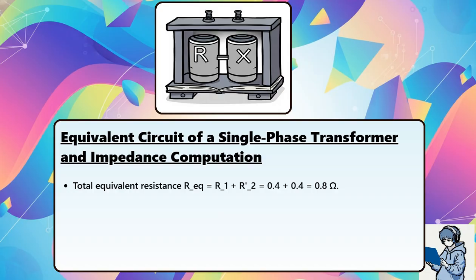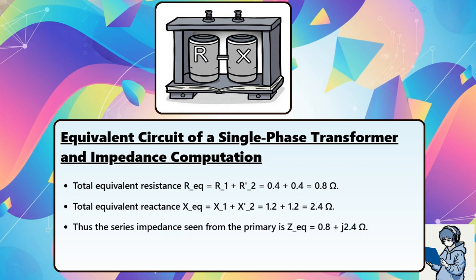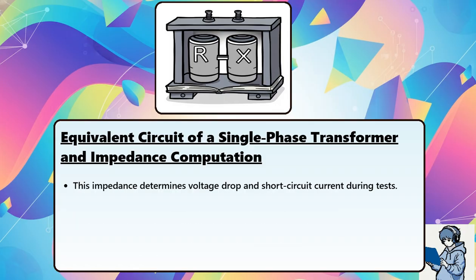Total equivalent resistance R_eq equals R1 plus R'2 equals 0.4 plus 0.4 equals 0.8 ohms. Total equivalent reactance X_eq equals X1 plus X'2 equals 1.2 plus 1.2 equals 2.4 ohms. Thus, the series impedance seen from the primary is Z_eq equals 0.8 plus j2.4 ohms. The magnitude Z_eq equals the square root of 0.8 squared plus 2.4 squared, approximately 2.53 ohms. This impedance determines voltage drop and short circuit current during tests.